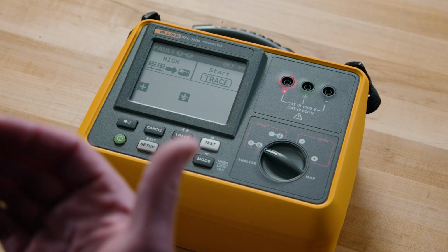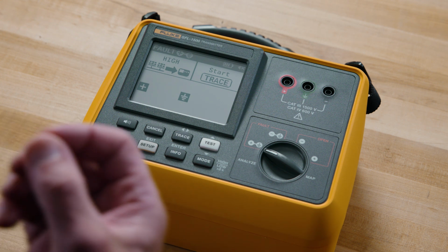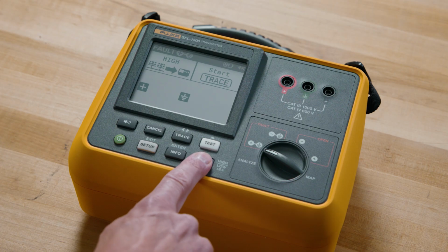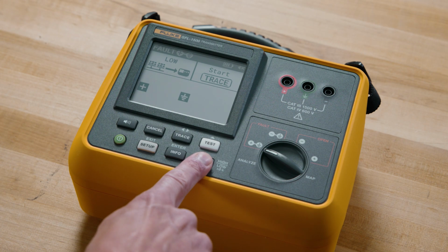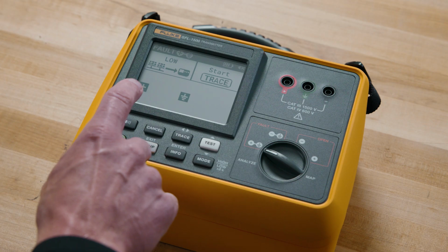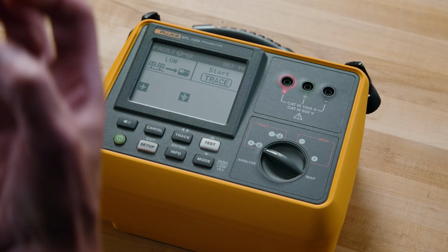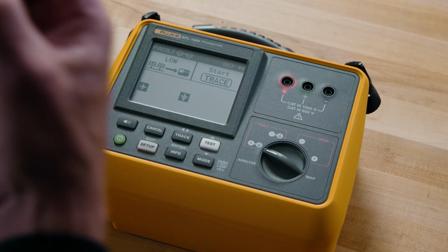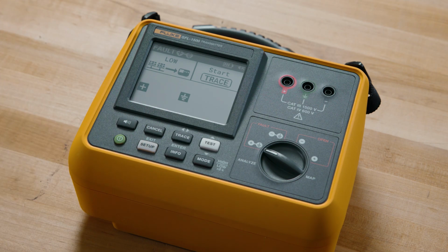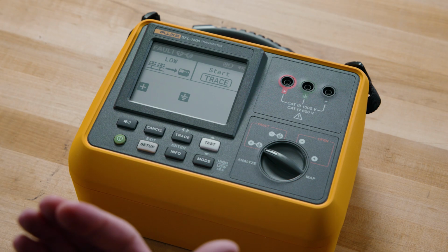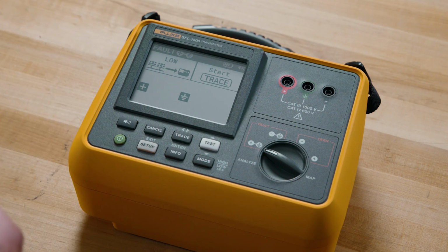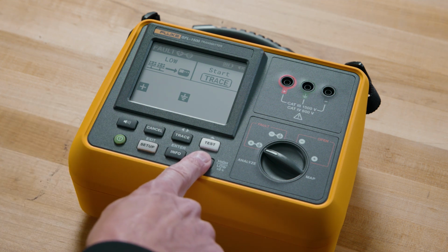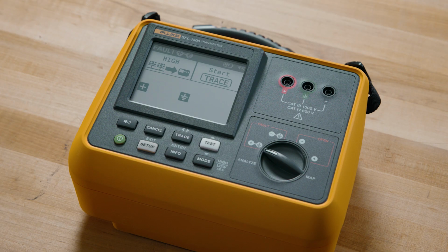In some cases, for example, installations with high parasitic capacitance where you're seeing a signal across the array, you can hold the Mode button down for 2 seconds and it will switch it from a high signal to a low signal. The low signal, because it has a lower current value, will flow through high resistance connections easier than the high signal. In the cases of solid ground faults with low resistance, the high mode will typically be more effective. Holding it down for 2 more seconds will return it back to high mode.